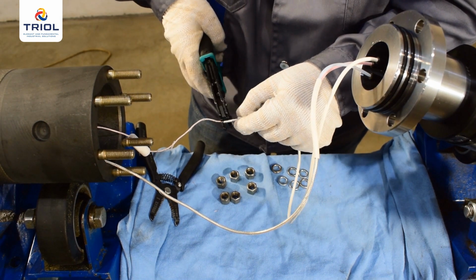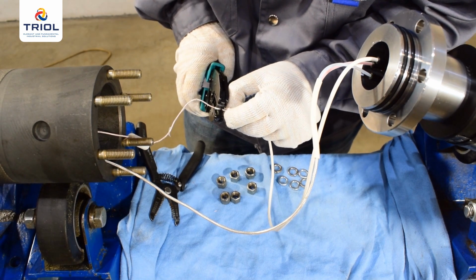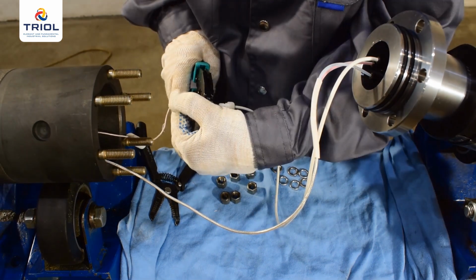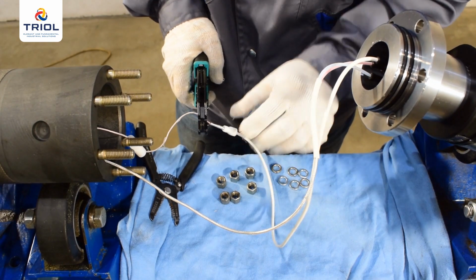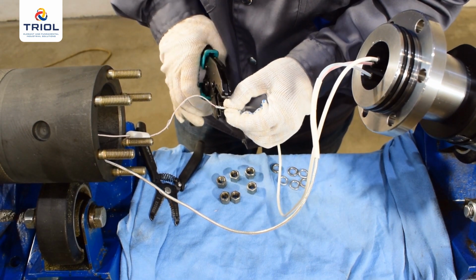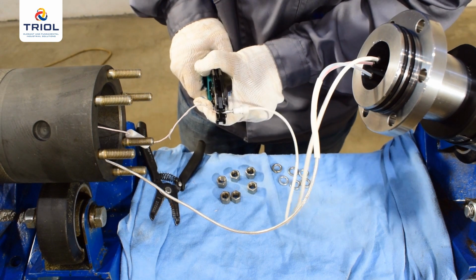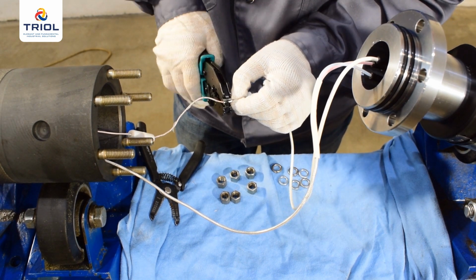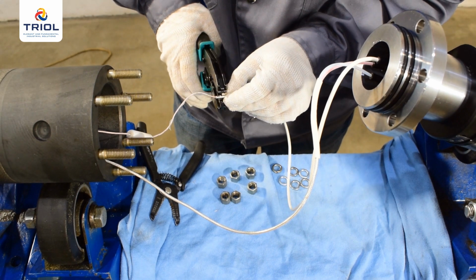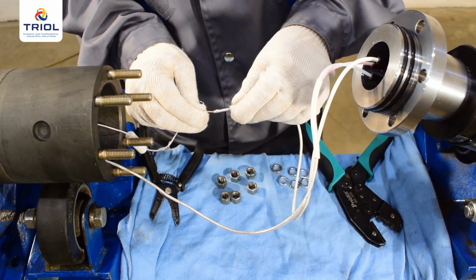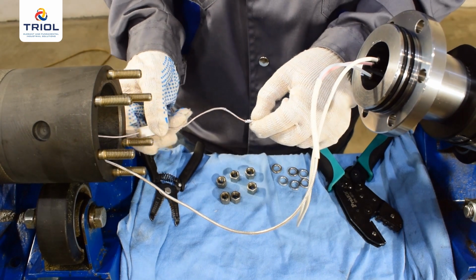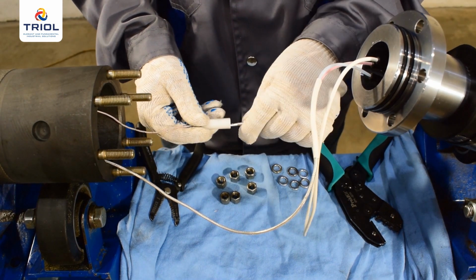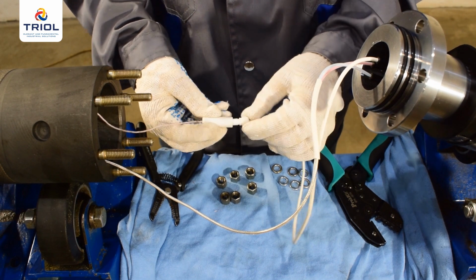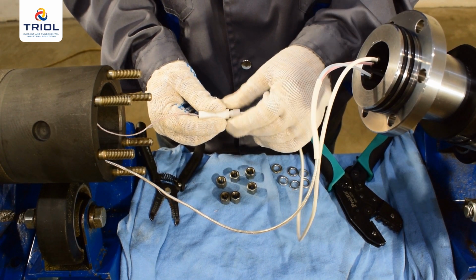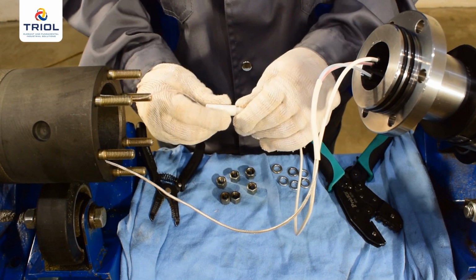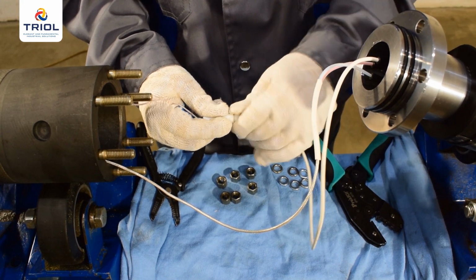Insert the threaded wire into the crimped sleeve on the other side and crimp with pliers in 2 places. Crimping points are at the beginning of the sleeve and at 2 to 3 millimeters from the special groove in the very center of the sleeve. Pull the wire and the sleeve in different directions. Make sure they are firmly fixed and connected. Screw on the insulating container cap. This will protect the connection from possible contact with metal parts of the motor. Pull the wires in different directions. Everything is secure and ready to be installed in the motor.